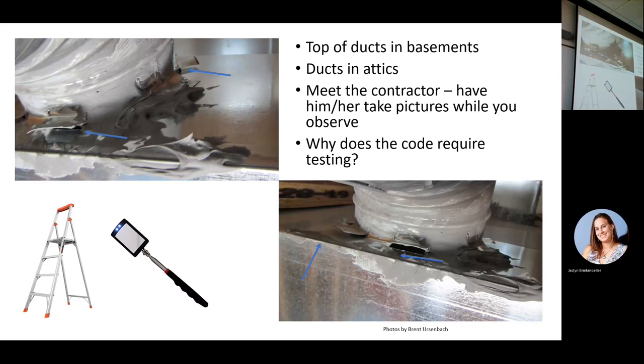so it's up to you if you want to accept it, because we didn't adopt the 18. But the 15 code says all your longitudinal seams on any snap lock duct has to be sealed. So that would be the whole snap lock seam, top and bottom. And where else? What else is snap lock? Round pipe.